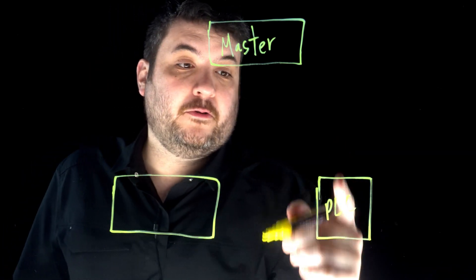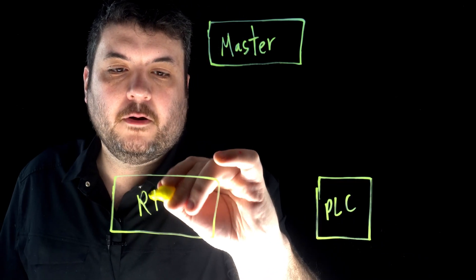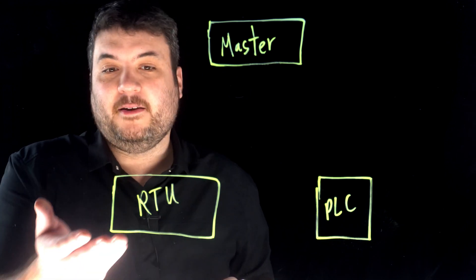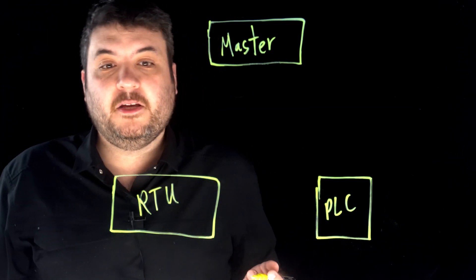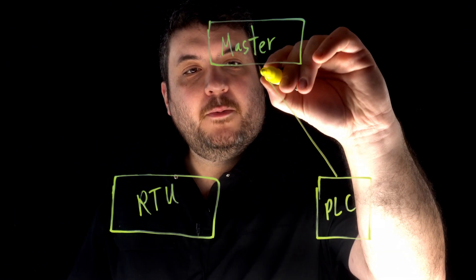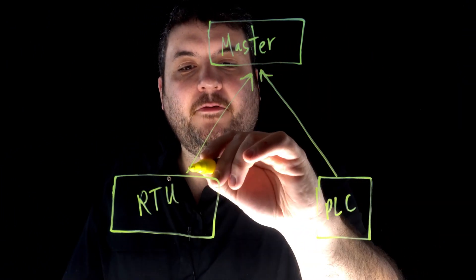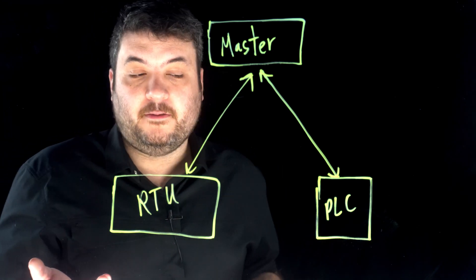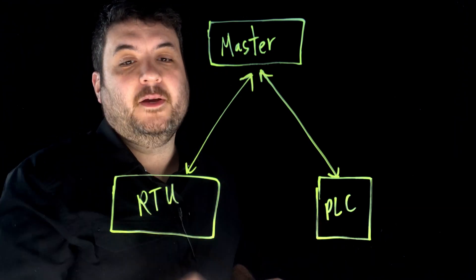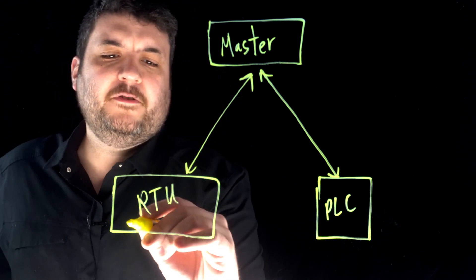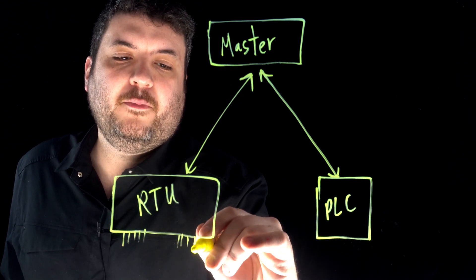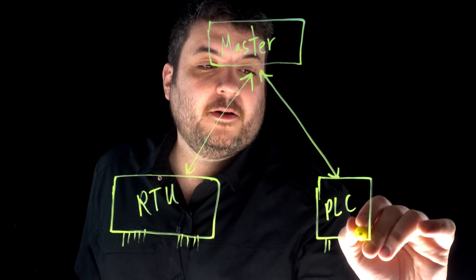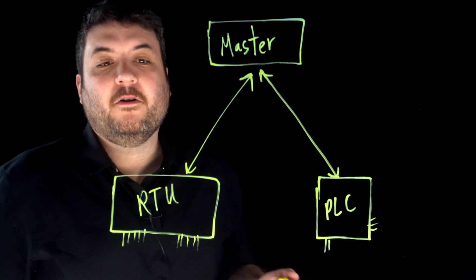When you have a PLC — a programmable logic controller — or an RTU, a remote terminal unit or remote telemetry unit, there's not a whole lot in those names that really matter, so we tend to just use short acronyms. Both of these are going to be communicating back to a master, and the master can send them commands. But you start to see differences in capacity. An RTU will tend to have lots of inputs, lots of outputs, a lot of intelligence — whereas a PLC might just have maybe a few inputs and a couple outputs. It's just a smaller capacity usually.